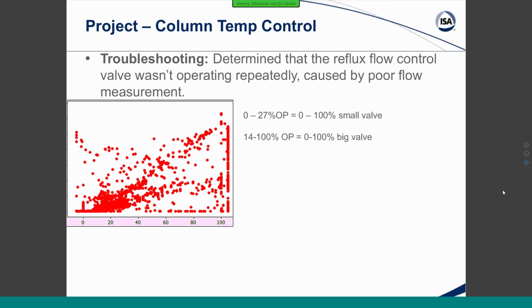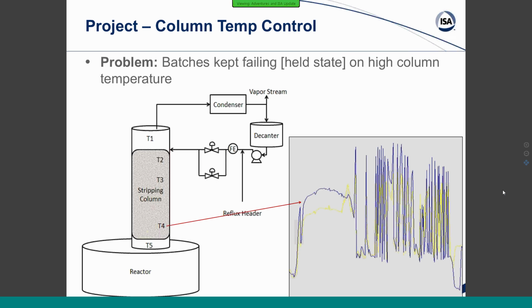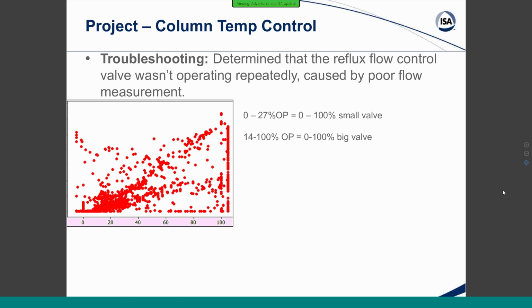So we started troubleshooting and eventually began to look at the instrumentation. Remember, we've got that flow element followed by the two control valves on a split range controller. The red dots here are the output of that split range controller compared to the flow. It kind of looks like somebody took a shotgun at it, which means that we've got really, really bad replication. So for a given output on the split range controller, you have absolutely no idea what your flow is going to end up being.